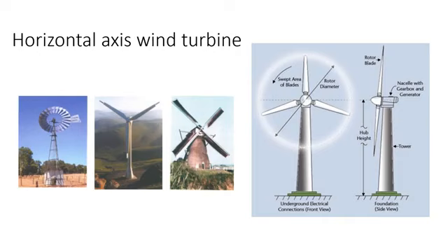Since a tower produces turbulence behind it, the turbine is usually positioned upwind of its supporting tower. Turbine blades are made stiff to prevent the blades from being pushed into the tower by high winds. Additionally, the blades are placed a considerable distance in front of the tower and sometimes tilted forward into the wind a small amount.